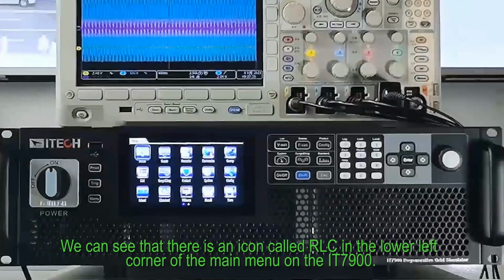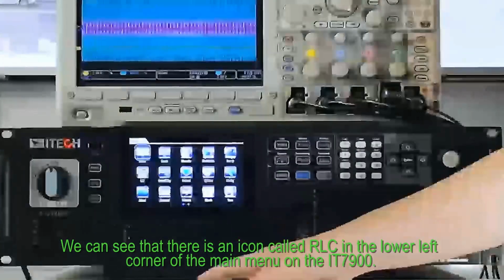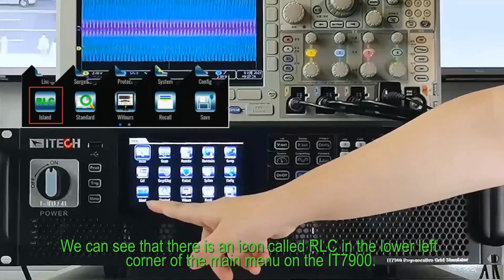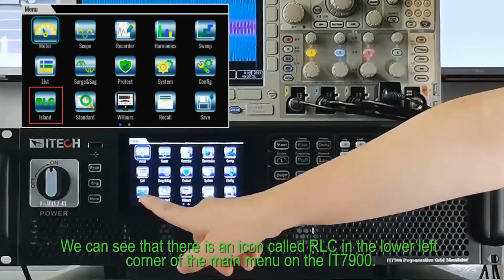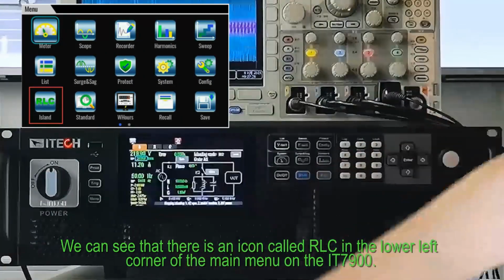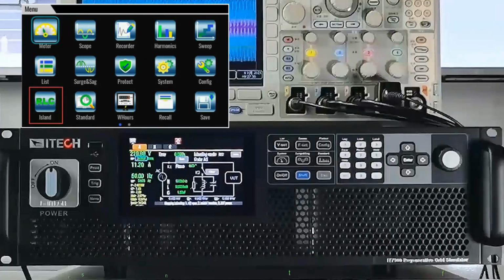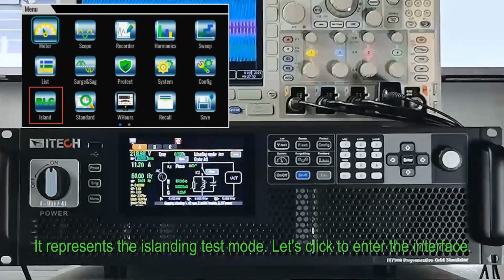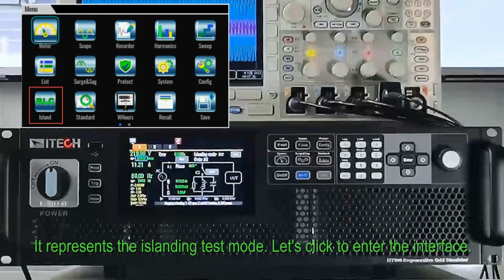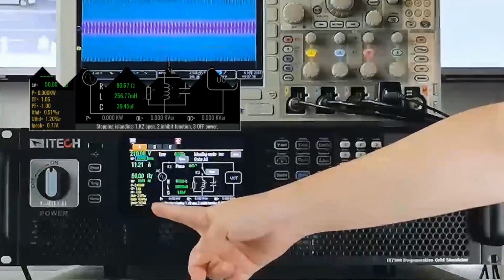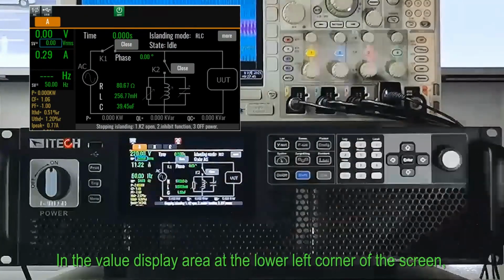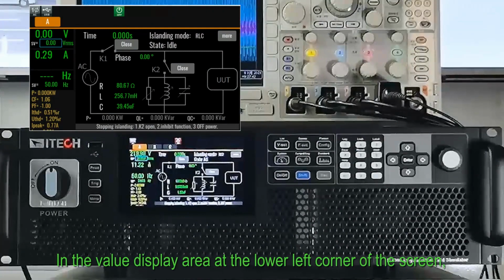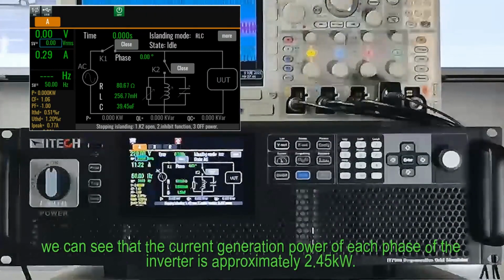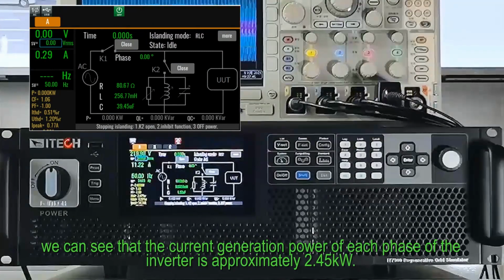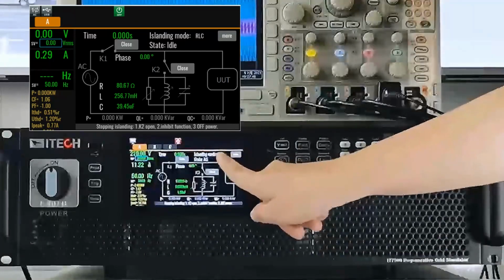We can see that there is an icon called RLC in the lower left corner of the main menu on the IT7900. It represents the islanding test mode. Let's click to enter the interface. In the value display area, the lower left corner of the screen, we can see that the current generation power of each phase of the inverter is approximately 2.5 kW.